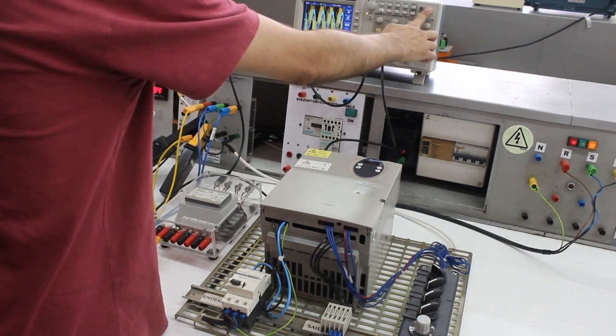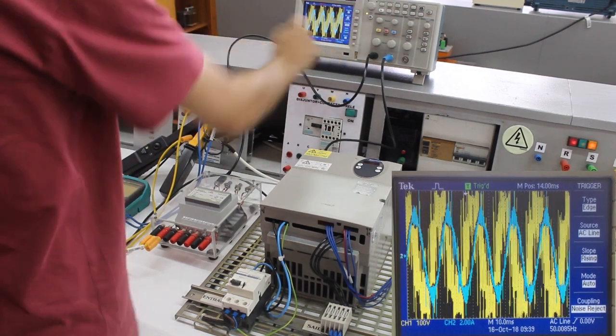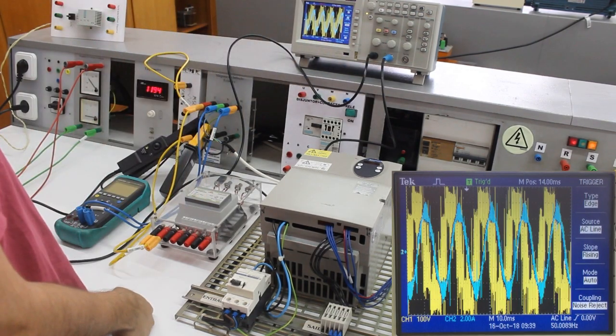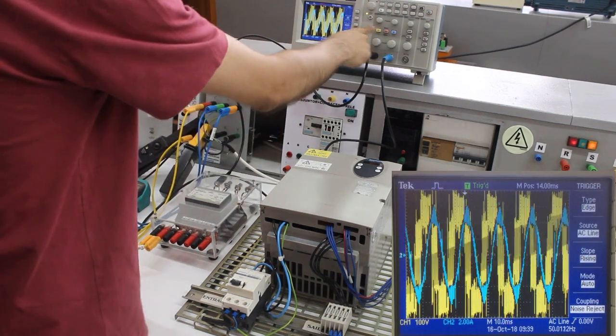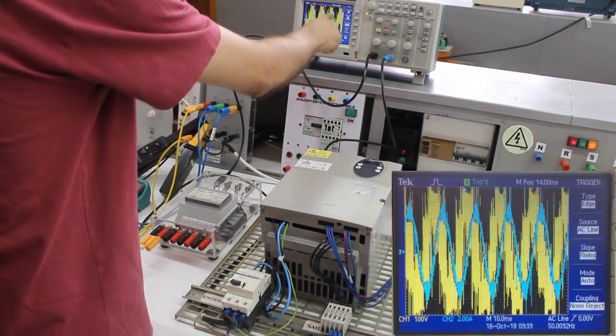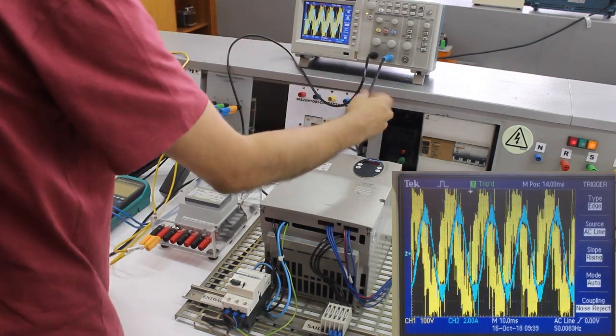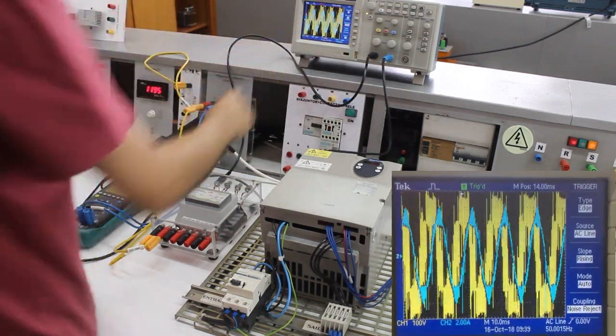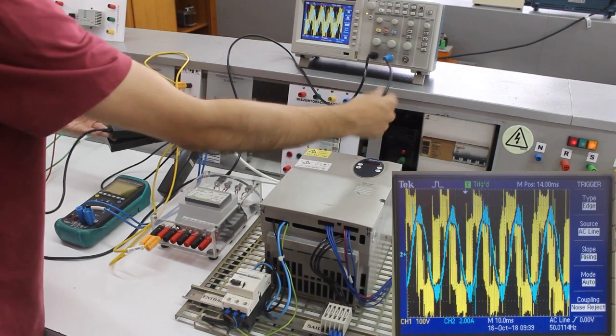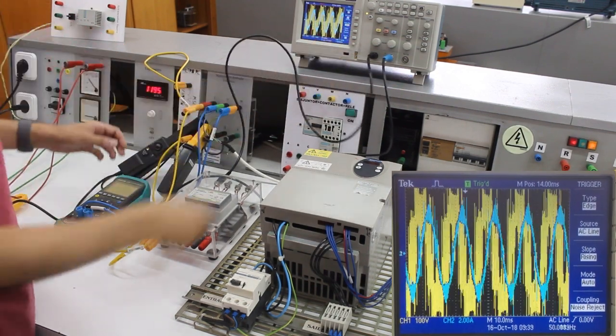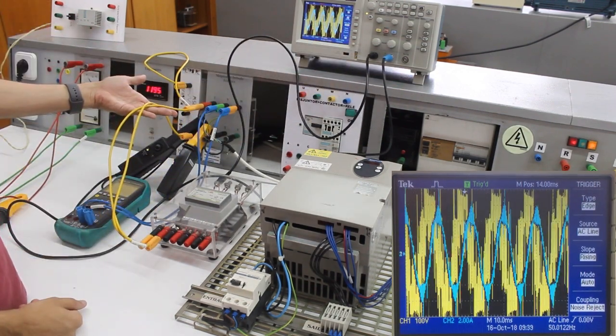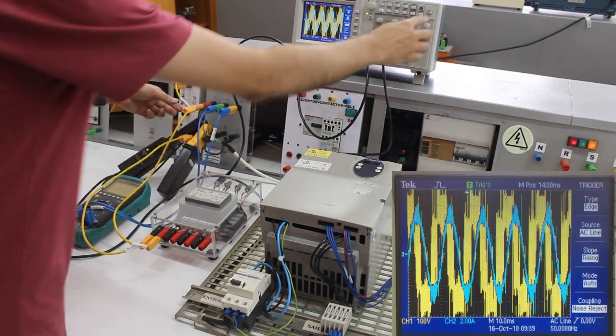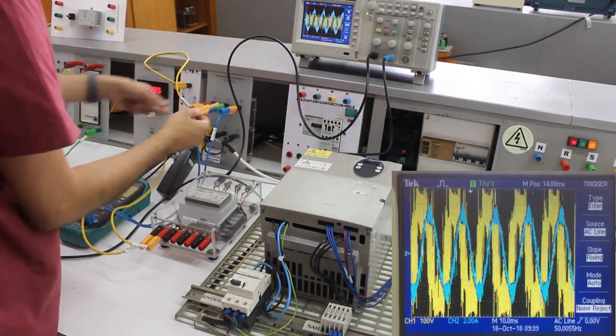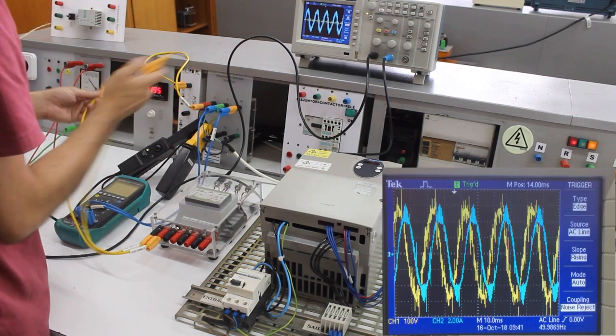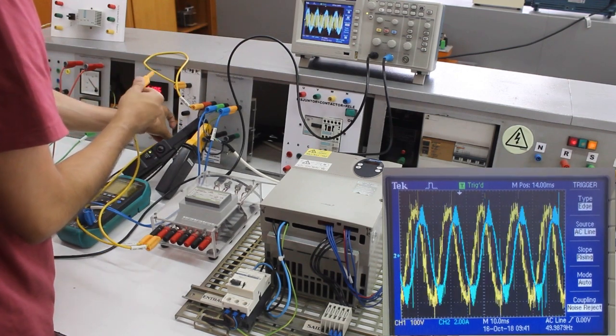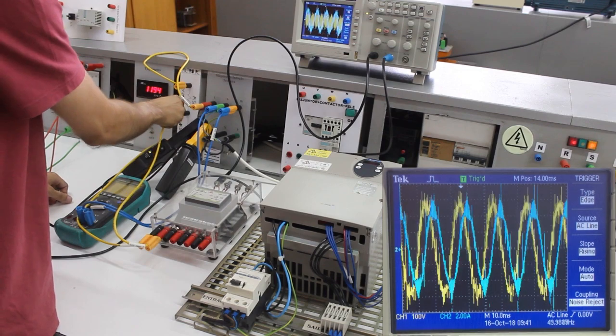With the machine running, let's look at the voltage and current at the terminals of the induction machine. In the yellow line you have the voltage with a higher harmonic content that comes from the variable speed drive, and in the blue line you have the current with a lower harmonic content. This phenomenon for the current is based on the impedance of the induction machine that filters the higher harmonics of the voltage. You can use a low pass filter to remove the higher harmonics of the voltage and remain with only the lower.